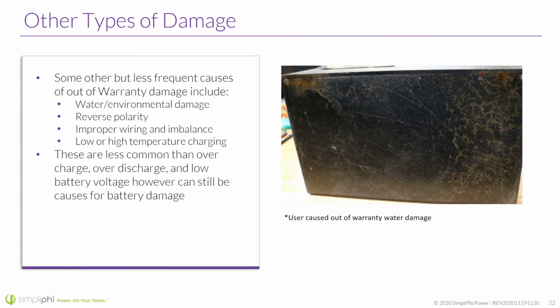Reverse polarity, I've seen a few of these, that's never fun. The battery will do its best, but if you keep pushing it, it's going to eventually not be able to protect itself from that. Improper wiring and imbalance, this one's pretty uncommon, but I've seen it. Maybe this has to do with torque specifications, or you're running everything to a small DC bus that can't handle it. And low or high temperature charging. This one is really uncommon.